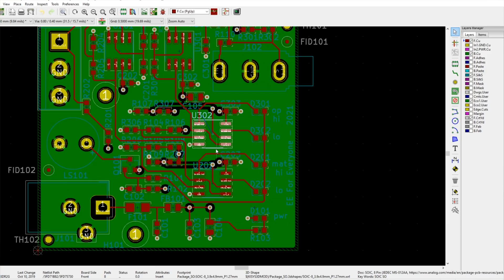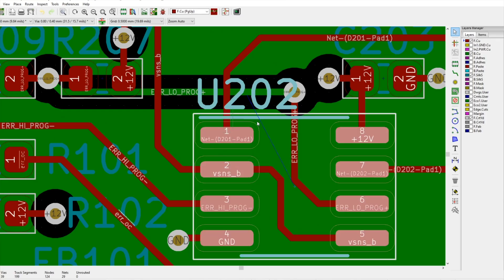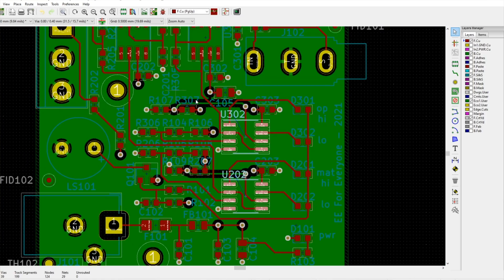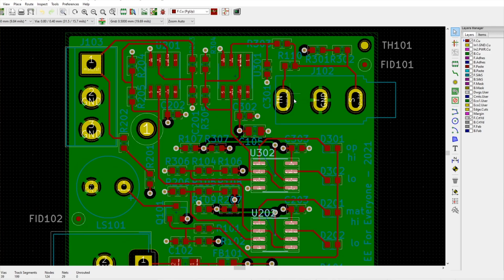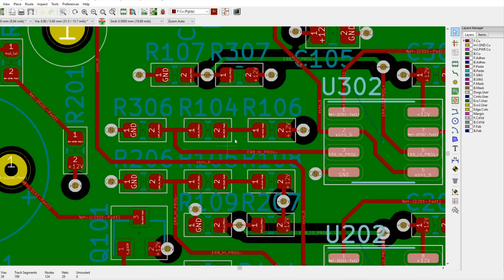These two ICs, U302 and U202, these are the two comparators that are comparing the monitored signals. So you have current source, or the resistors, the current limiting resistors to the power rail coming in to the test, coming back, and we're monitoring the impedance between the test and ground. That's what we're measuring. And same thing for the mat. We have a couple resistor networks.